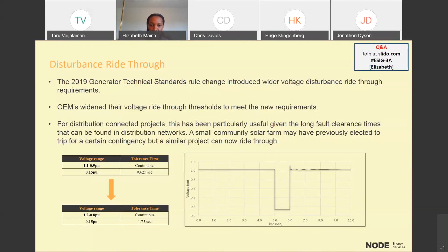So we've got an opportunity now that some of these smaller projects that historically would have had to trip based on their capability. But with advancements on the OEM side, some of these projects are now able to ride through longer duration faults that previously would have required tripping, which had added to the whole challenge of having more and more projects tripping when there's a disturbance somewhere in the network.